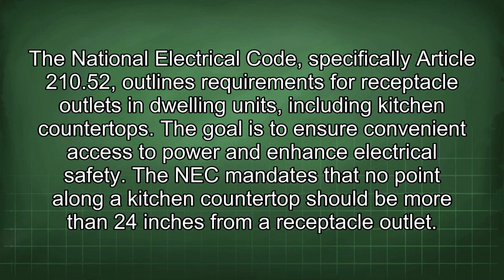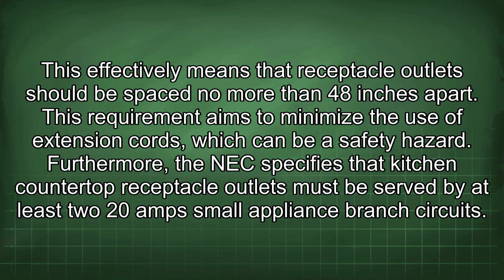The National Electrical Code, specifically Article 210.52, outlines requirements for receptacle outlets in dwelling units, including kitchen countertops. The goal is to ensure convenient access to power and enhance electrical safety. The NEC mandates that no point along a kitchen countertop should be more than 24 inches from a receptacle outlet. This effectively means that receptacle outlets should be spaced no more than 48 inches apart. This requirement aims to minimize the use of extension cords, which can be a safety hazard.